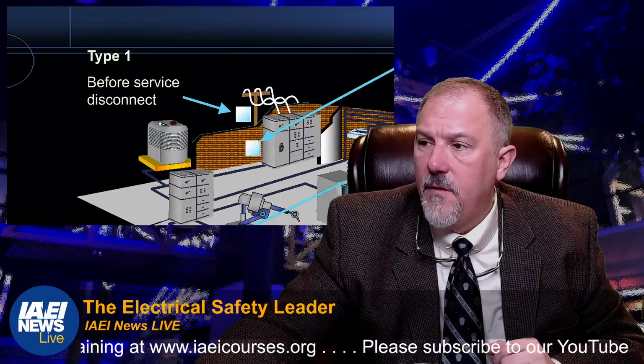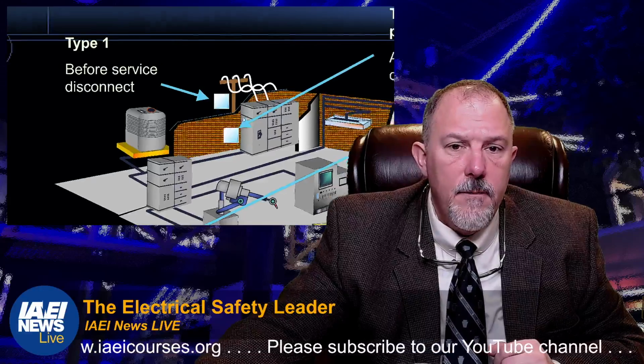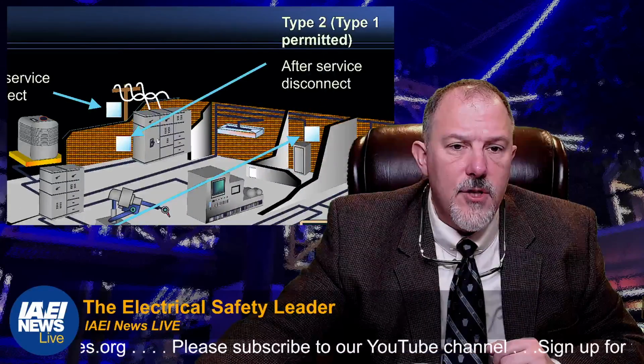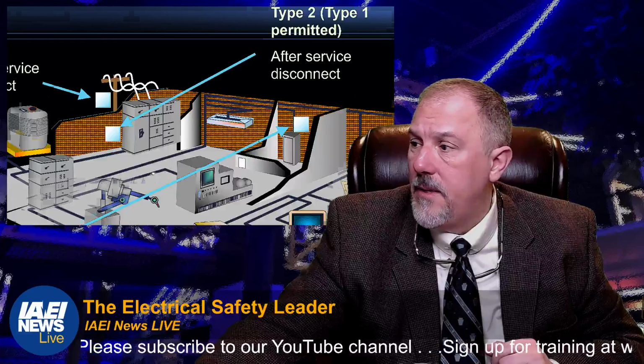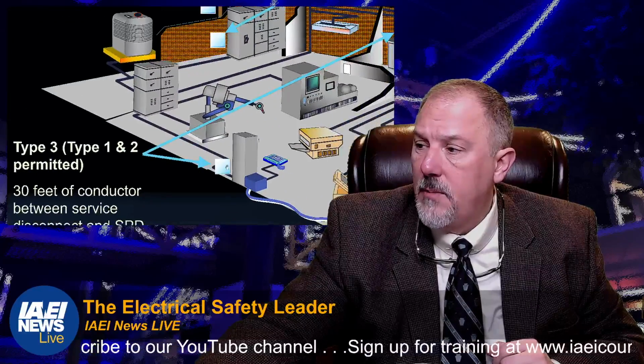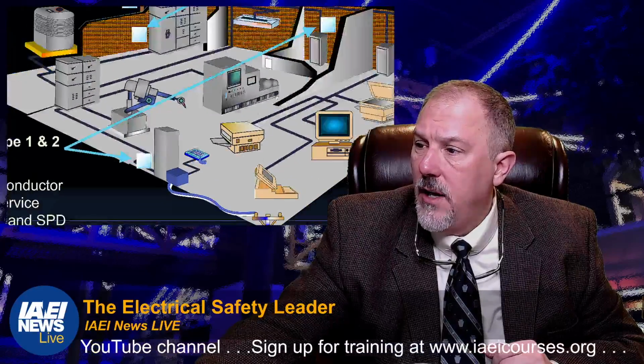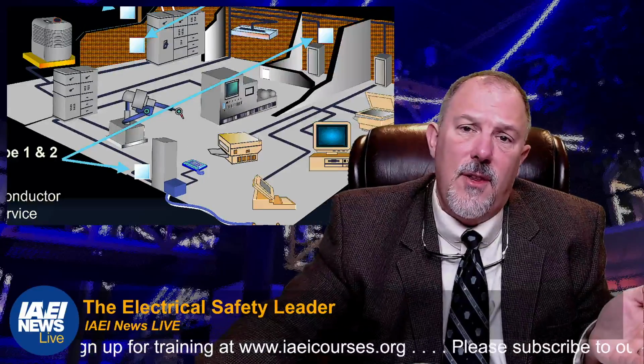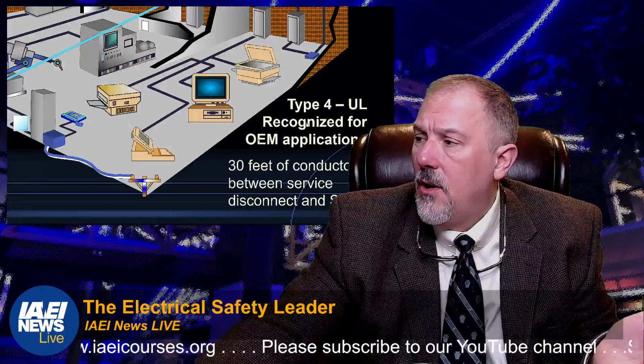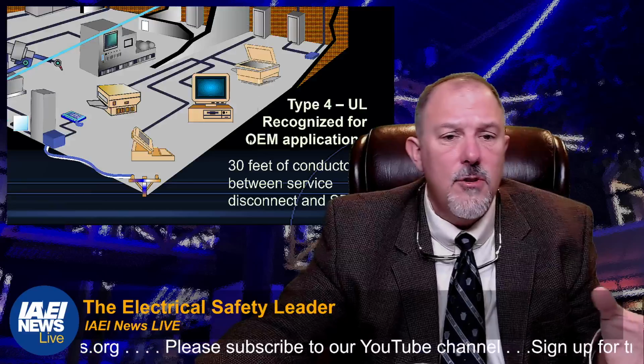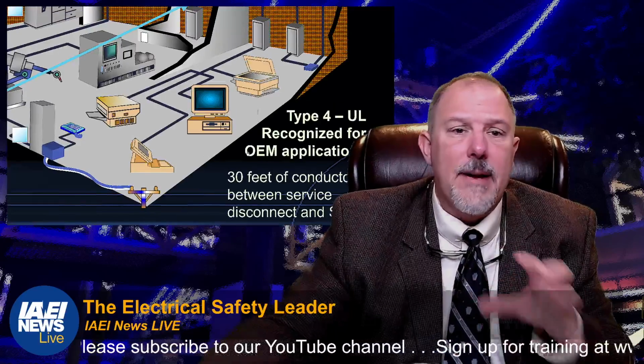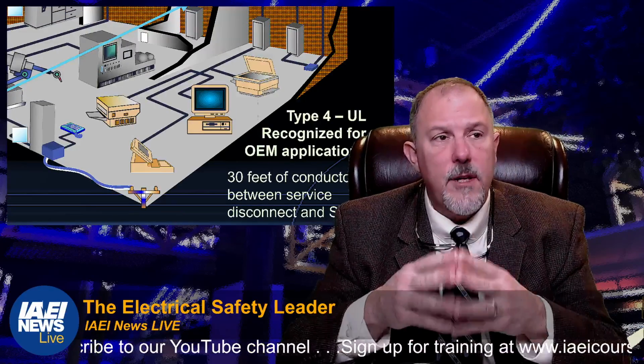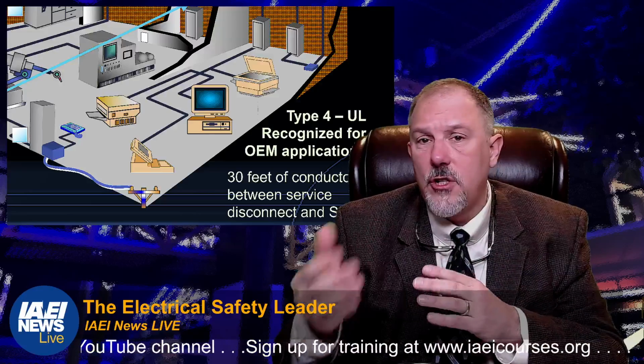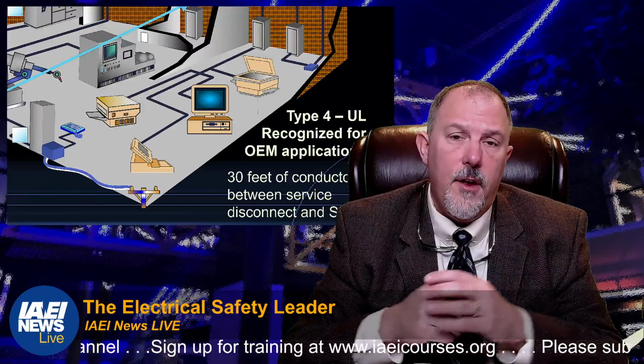So your type 1 is before that service disconnect. Your type 2 is after the service disconnect. You'll see it in service equipment. Your type 3s would be at your point of utilization at your equipment. You'll see these like, I don't know, in data centers down close to the computers and things of that nature. And then your type 4s are recognized for OEM applications. So those are built into the products themselves. You wouldn't be installing those as an electrician or electrical contractor externally. They would be built in.